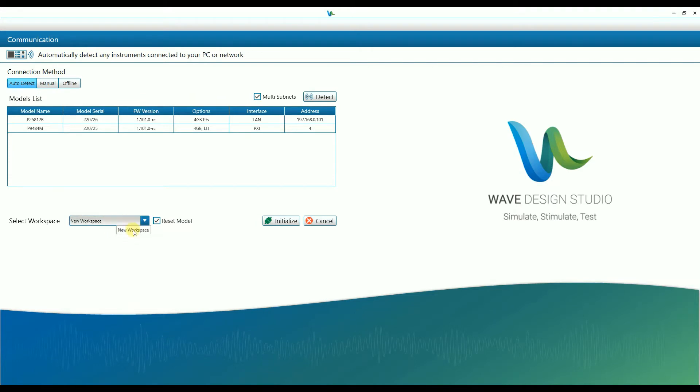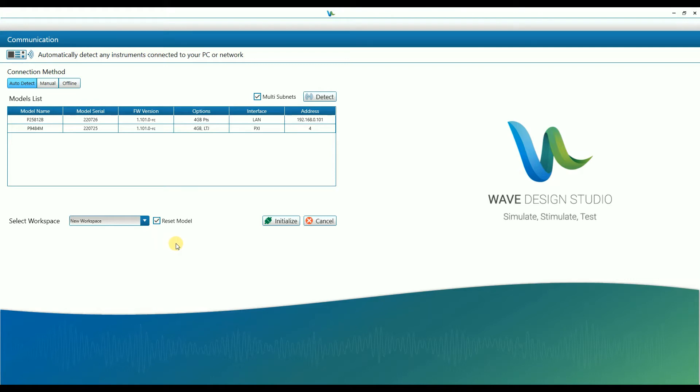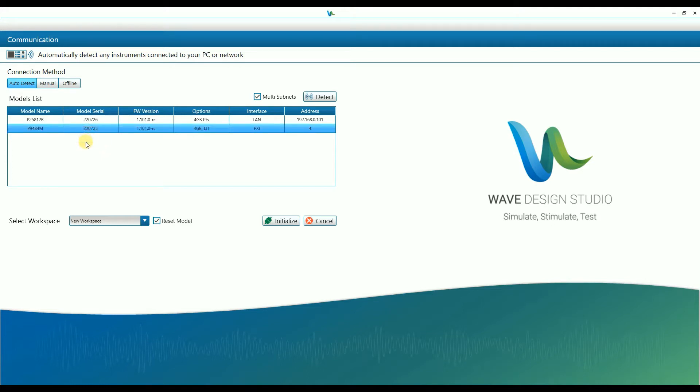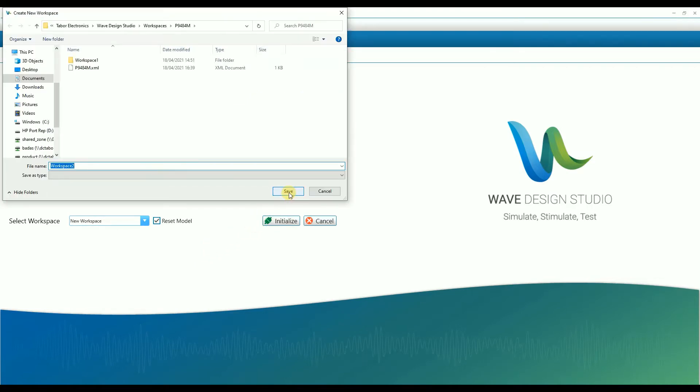WDS uses workspaces. A workspace includes a full instrument setup, and this way users can load a specific workspace and the instrument will be fully configured, including waveforms, scenario, and run modes. In the case of multiple units that are identified, select the unit that you wish to control and then select whether to use a new workspace or load a workspace, and then click on initialize.